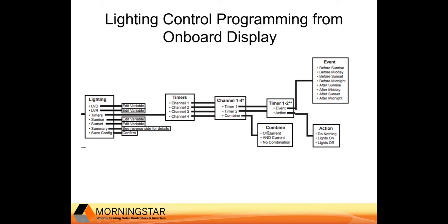You will also note the combine functions. These are Boolean logic functions used to combine the timers and it is important that these are used. The function OR means one event or the other triggers their respective event. AND means this event and that event must occur together for the event to trigger. Generally speaking, the OR function is the most commonly used. The combinations of logic available allow you to get very creative with what you want to make happen — you just have to plan it all out and think it through before programming.